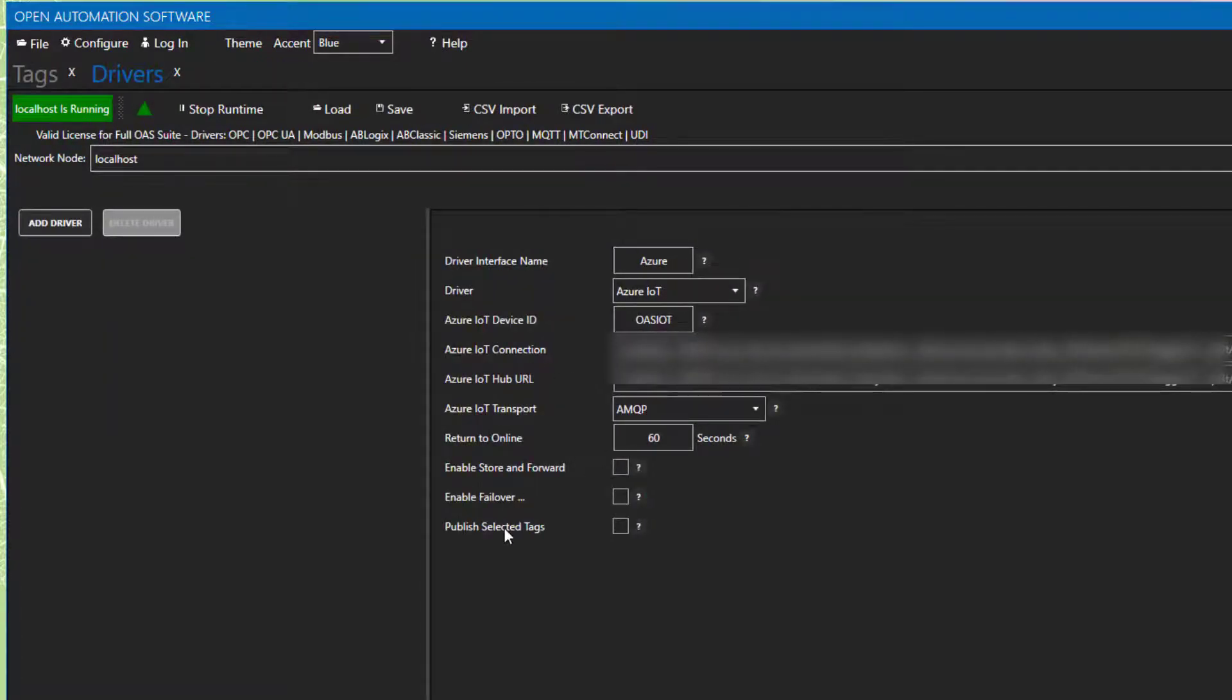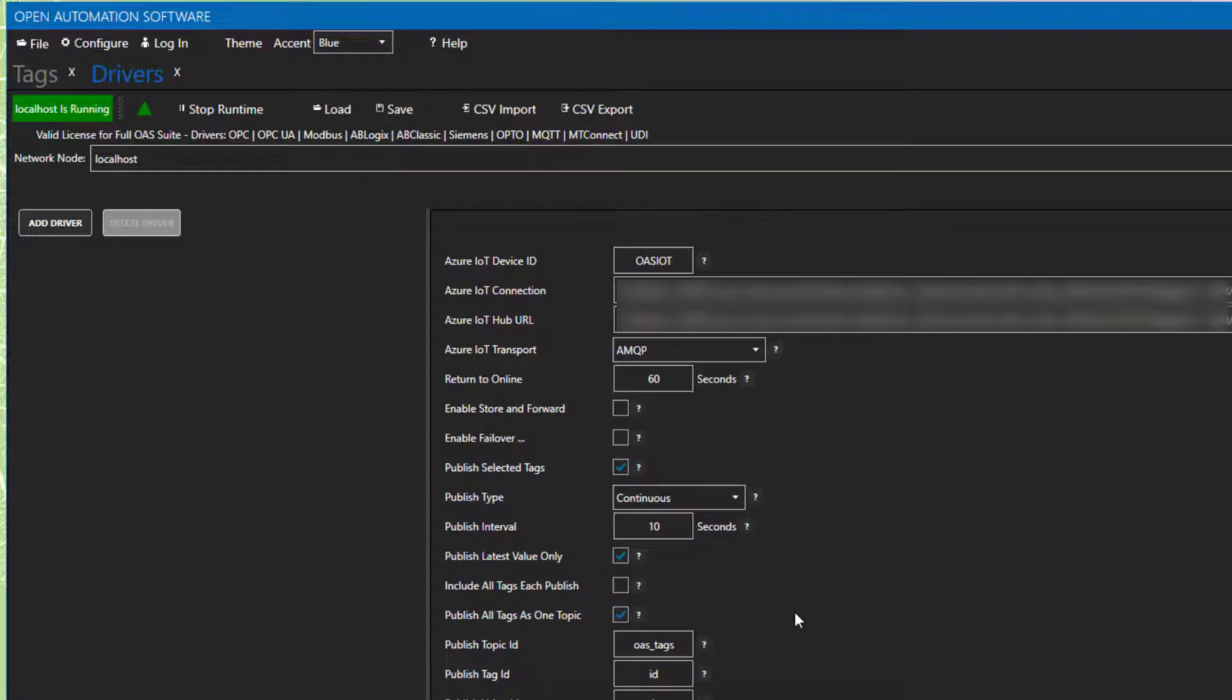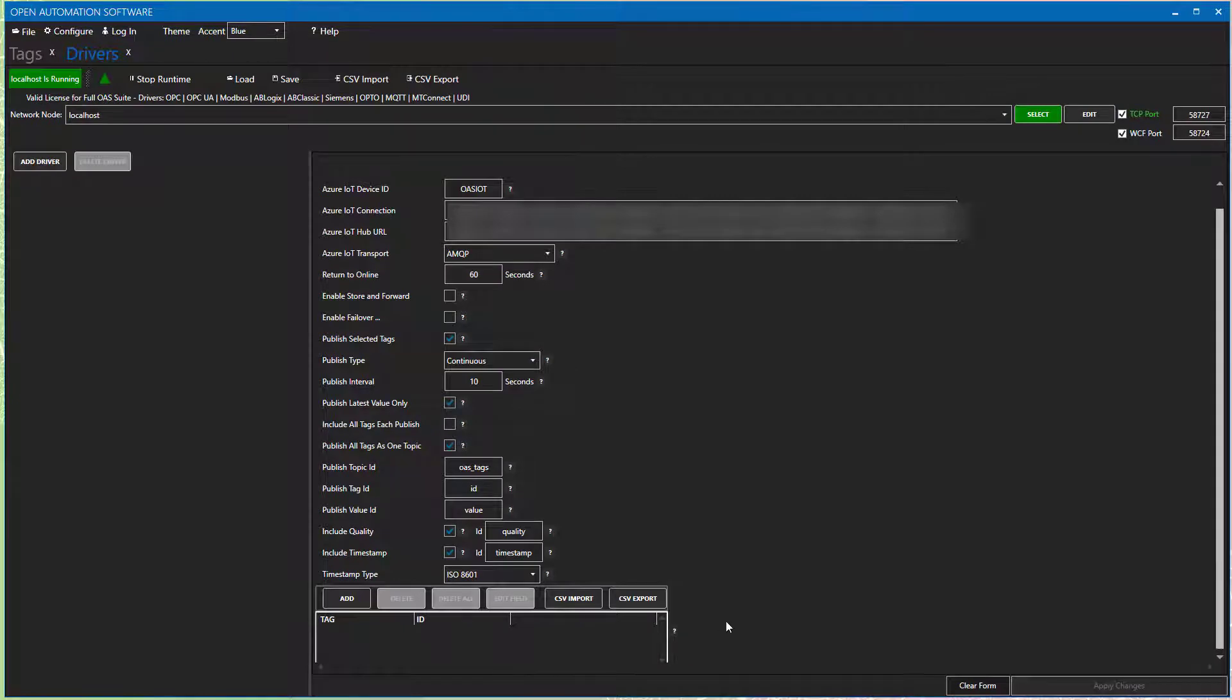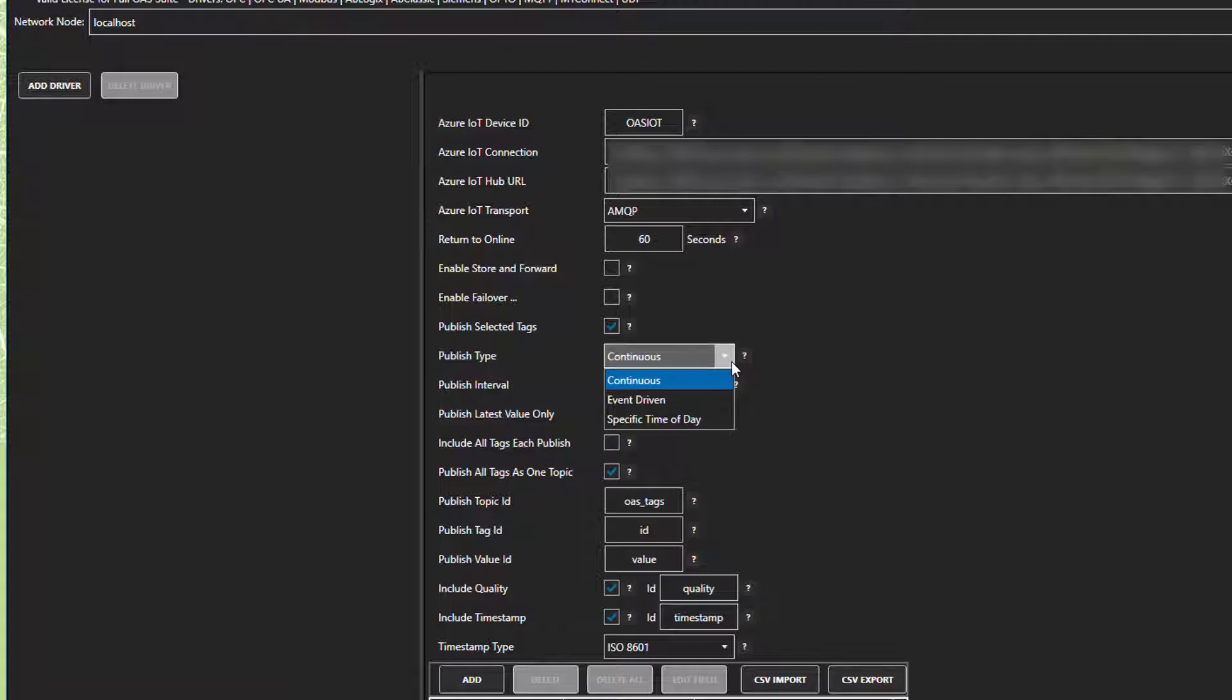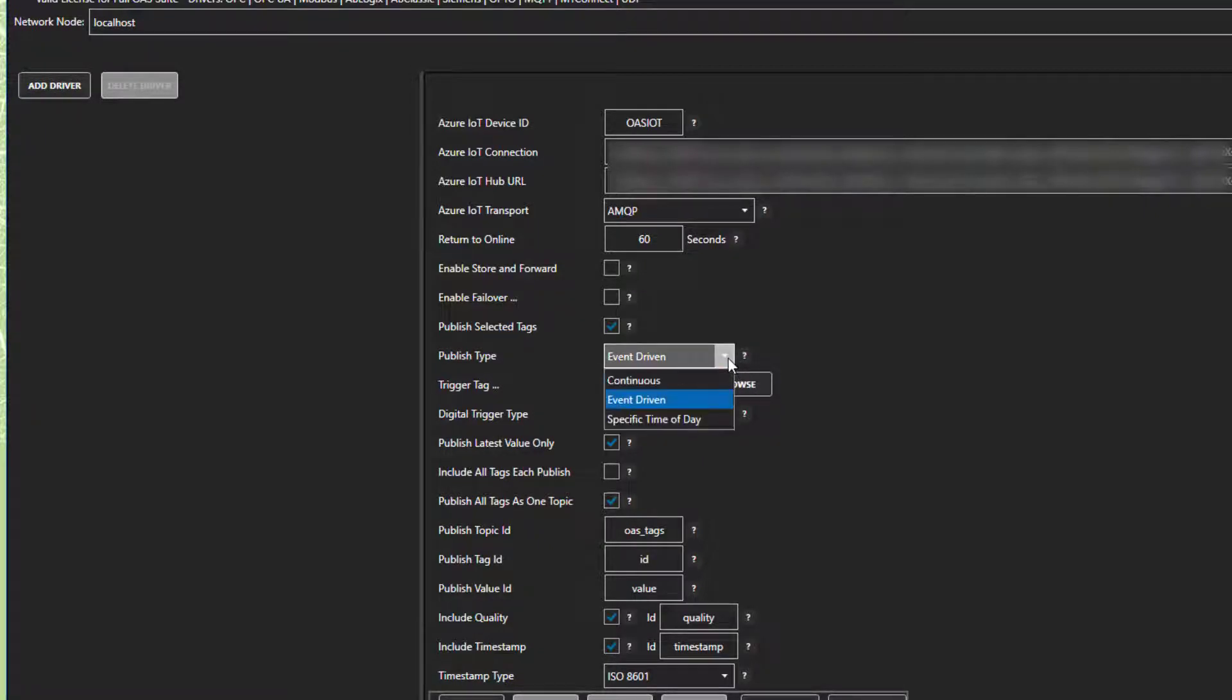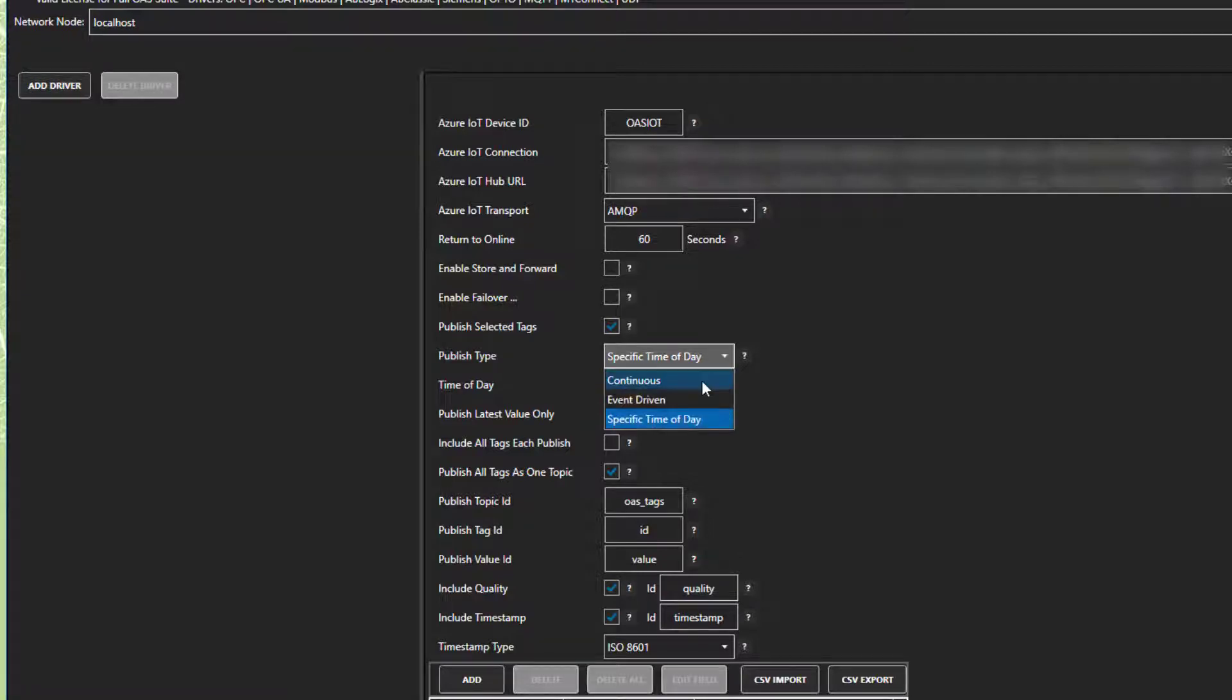Next, at the bottom of the interface, we are going to check the box for Publish Selected Tags. This will enable a whole new group of controls for the bulk tag publish. Down below, we will choose a list of tags we would like to publish. But first, let's start by looking at the publish settings. The first is a drop-down for publish type. With this, you can set the publish to be event-driven, and you are prompted to select a trigger tag to kick it off. There is also a specific time of day, and you would enter it here to have your bulk publish occur daily at that specified time. The default is continuous, and you specify the publish interval in seconds below. I am going to leave it at this 10-second rate for now.